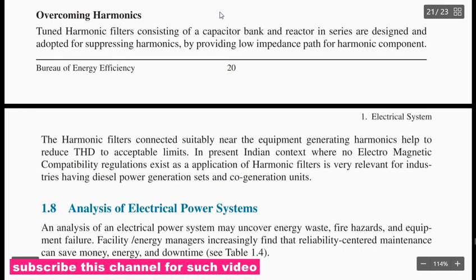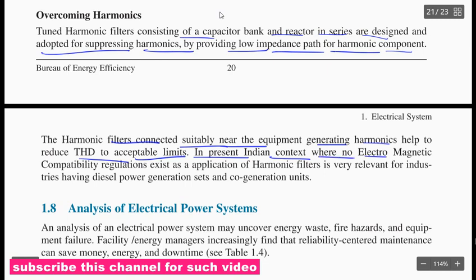Overcoming harmonics. A tuned harmonic filter consists of a capacitor bank and reactor in series, designed and adapted for suppressing harmonics by providing a low impedance path for the harmonic component. The harmonic filter connected suitably near the equipment generating harmonics helps to reduce the total harmonic distortion to an acceptable limit. In the present Indian scenario, where no electromagnetic compatibility regulation exists, the application of the harmonic filter is very relevant for industries having diesel power generation sets and cogeneration units.